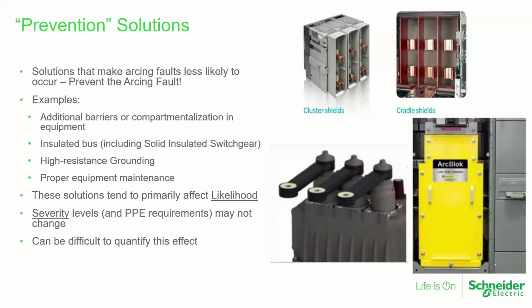It brings up, though, one thing that's kind of interesting about these prevention solutions. I say down there below, these solutions tend to primarily affect the likelihood of occurrence, right? So if you can take single line to ground faults to some extent, at least out of the equation, then yeah, you've reduced the risk that doing something or making a mistake inside a piece of equipment is going to create an explosive arc flash event. You may not, just by virtue of the high resistance grounding system, eliminate the probability altogether. Because even on an HRG system, you can still have a phase-to-phase fault or a 3-phase fault that would burn just as brightly as it would if it was solidly grounded.